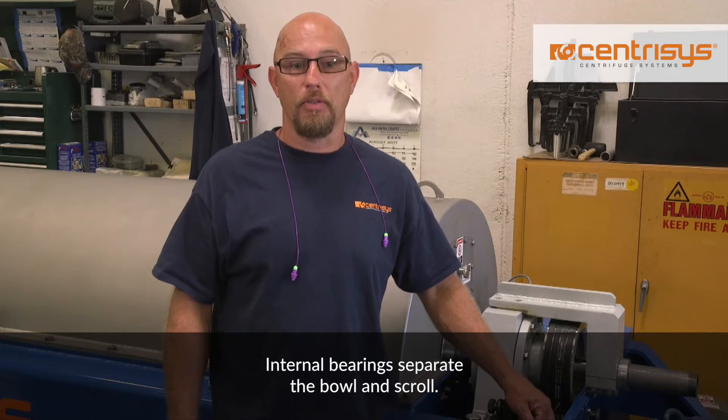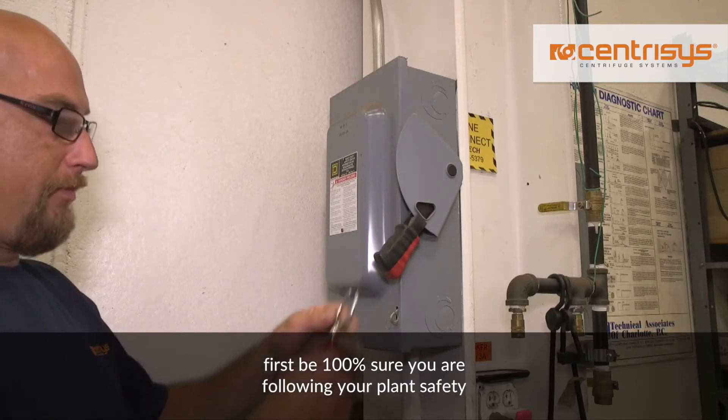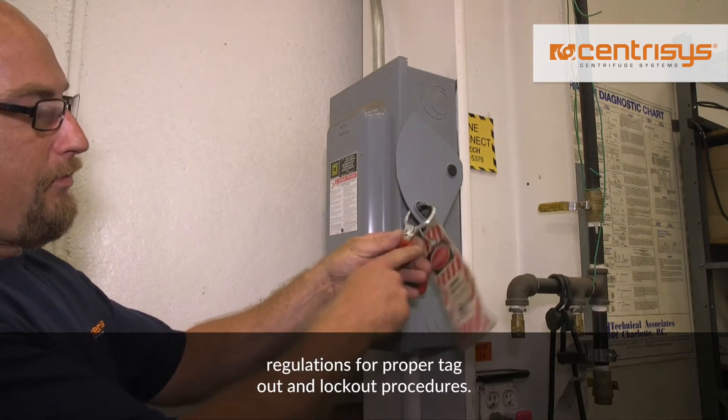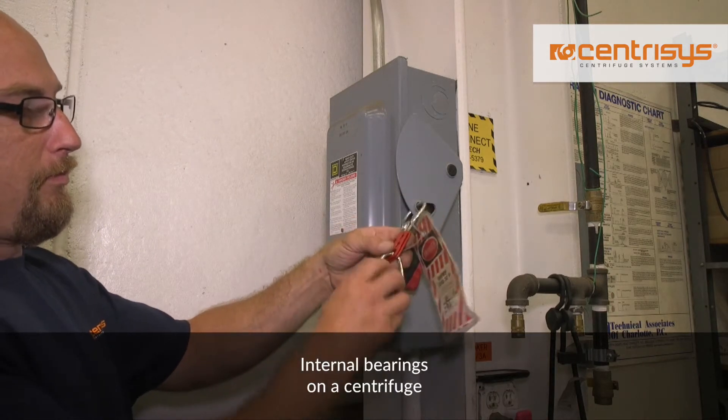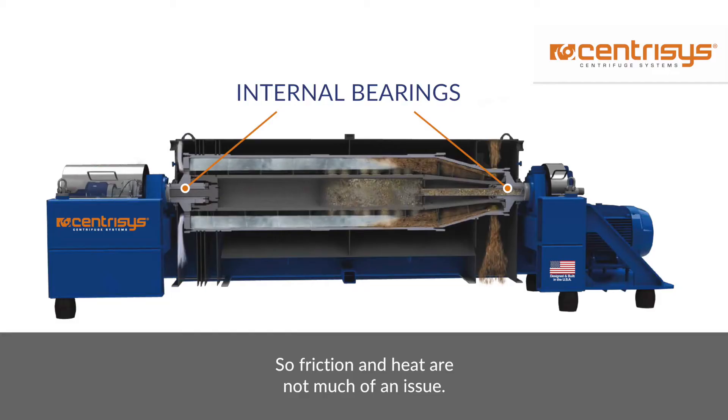Internal bearings separate the bowl and scroll. When greasing the internal bearings, first be 100% sure you are following your plant's safety regulations for proper tagout and lockout procedures. Internal bearings on a centrifuge operate at a very low speed, so friction and heat are not much of an issue, but your centrifuge bowl needs to be locked out.